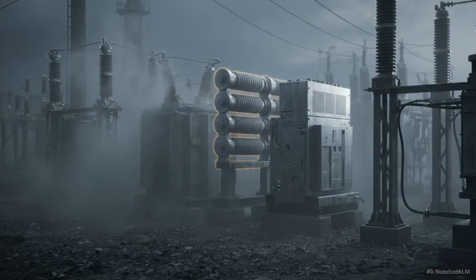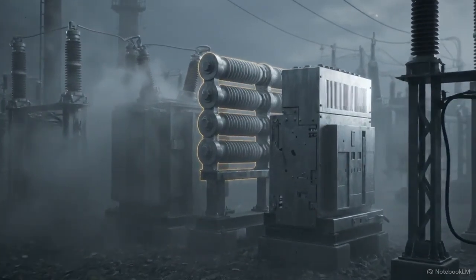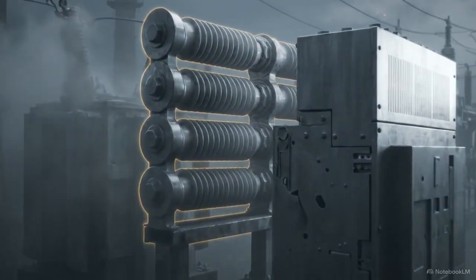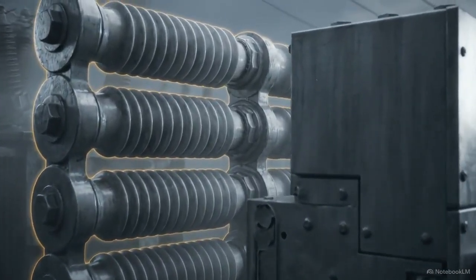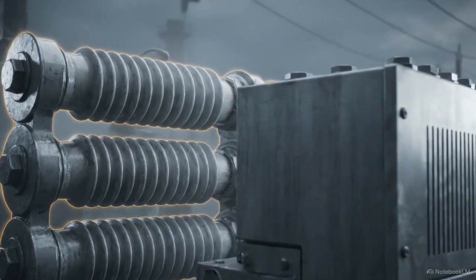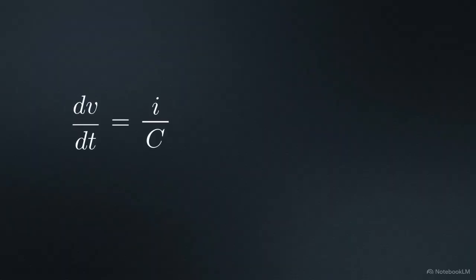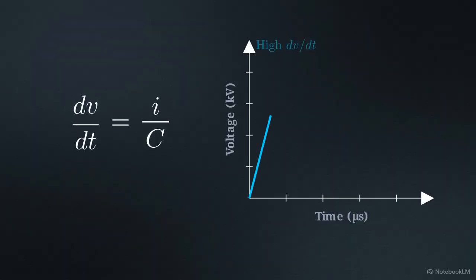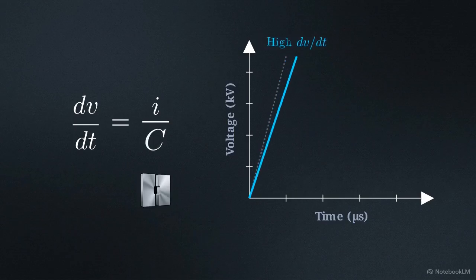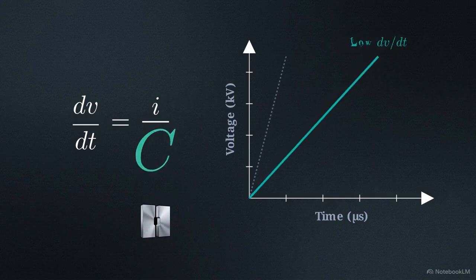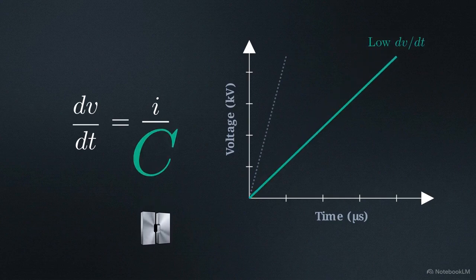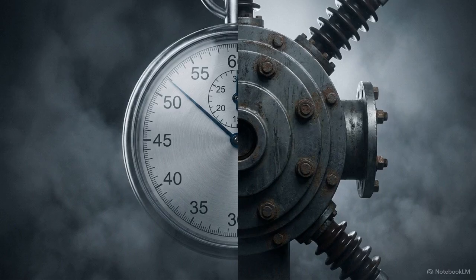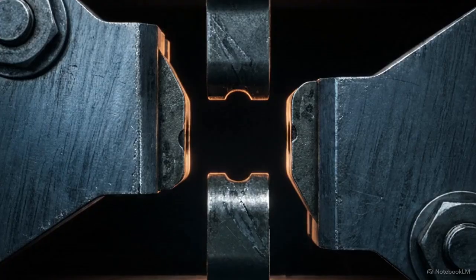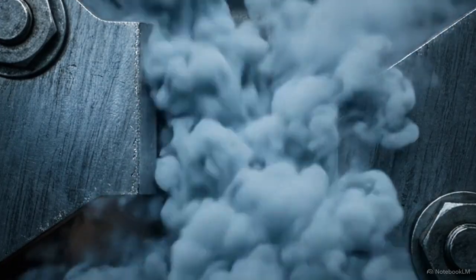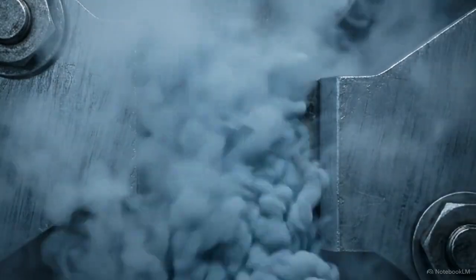Another strategy is capacitive mitigation. Engineers will install surge capacitors or capacitor voltage transformers directly at the breaker terminals. The logic here comes down to a simple relationship. The rate of voltage rise is equal to current divided by capacitance. By increasing the capacitance at the terminals, engineers physically slow the rate of voltage rise. By adding that capacitance, engineers act as timekeepers. They artificially slow the clock on the grid's voltage response, buying the breaker the vital microseconds it needs to recover.